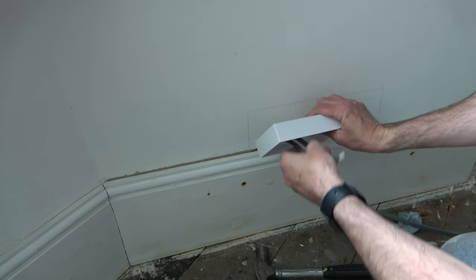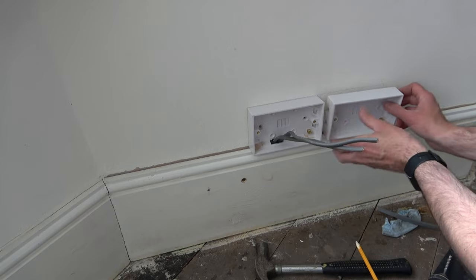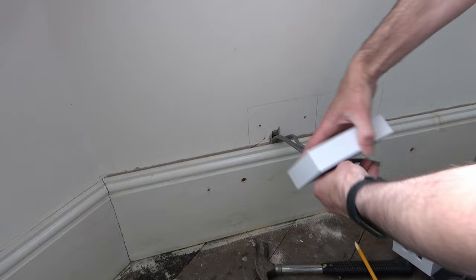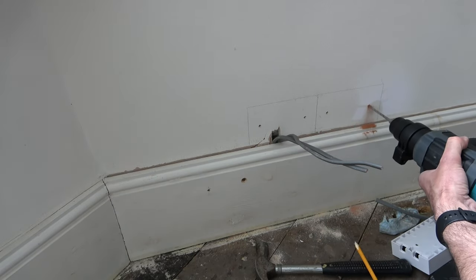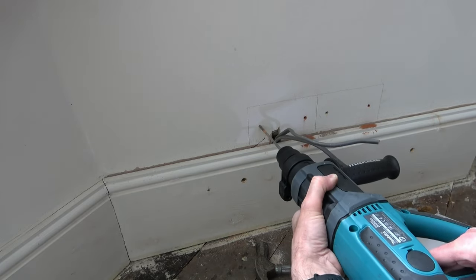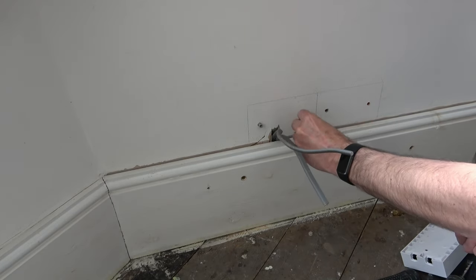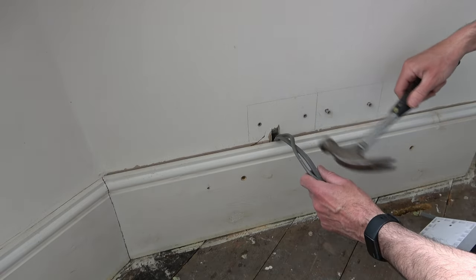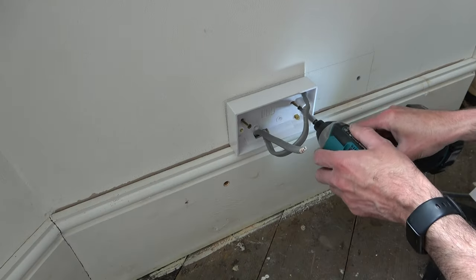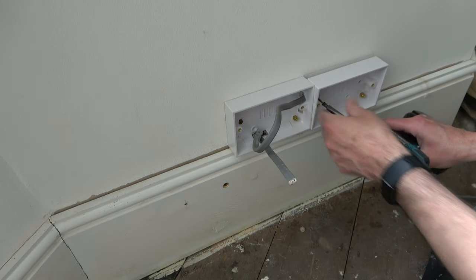I push the cables through the holes in the pattress box and place it into position. Then using a 5mm masonry drill bit, I drill through the holes in the back of the pattress box, marking the positions of the holes. I remove the pattress boxes from the wall and using a 6mm SDS drill bit in my SDS drill, I drive through the full size of the hole ready for the plugs — that's the correct size for the plugs I'm using. I keep everything clean with the Henry Hoover. Using the same Fischer Duopower plugs as earlier, I push them in by hand and follow up with a hammer. I push the pattress box back over the cables, manoeuvre into position, drive the screws into the plugs using my impact driver, then repeat the process for the other pattress box.